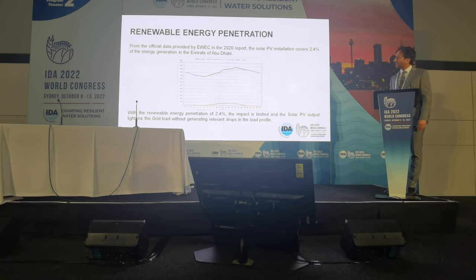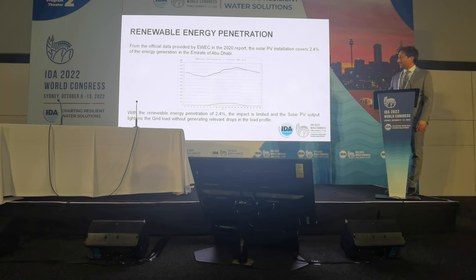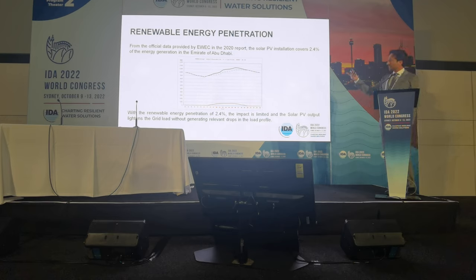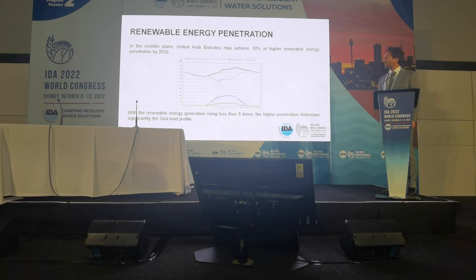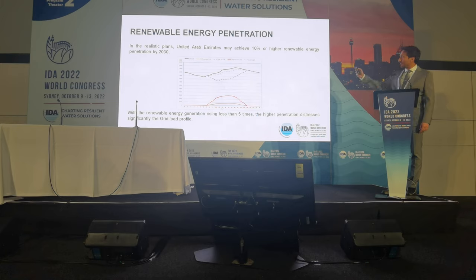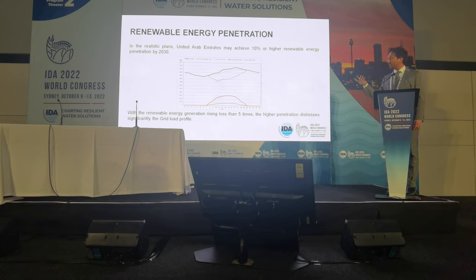This graph shows the production profile of Abu Dhabi. The orange on the bottom is the renewable production, which is only 2.4% of the total — very limited impact, and the network is resilient enough to accept this penetration without trouble. But if we increase to the 10% target — less than five times the current penetration — we get the duck curve. The duck curve, developed in California, shows that a big penetration of renewables has a huge impact on the production profile.